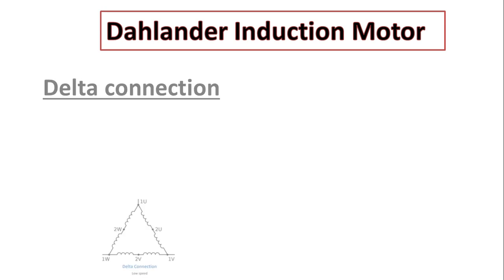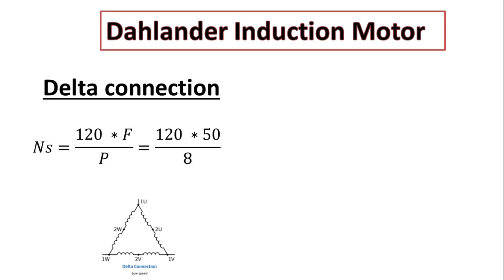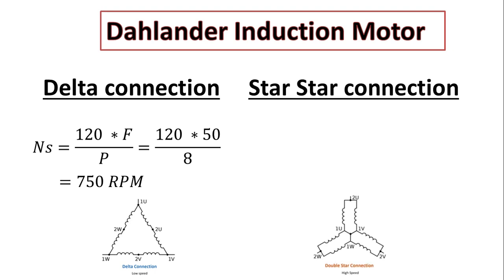So in case of delta connection, as you can see, we will connect the power supply to 1U, 1V, 1W. Here we will get eight poles. So inside this formula we will find that the synchronous speed will equal to 750 RPM. But in case of double star connection, we will only get four poles.